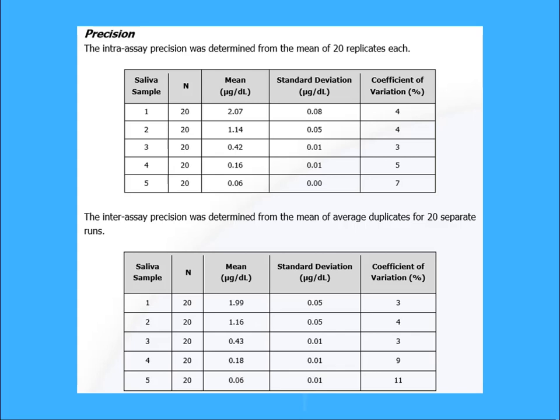So how can you determine what a good threshold should be for accuracy and precision limits? Often the manufacturer will define an acceptable limit within the kit insert, but if they don't, you can set your own.